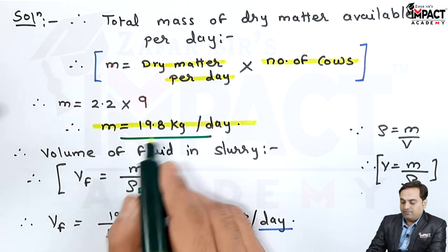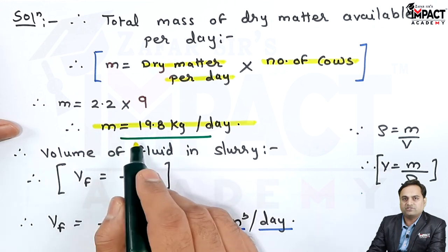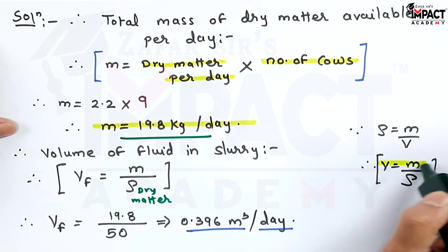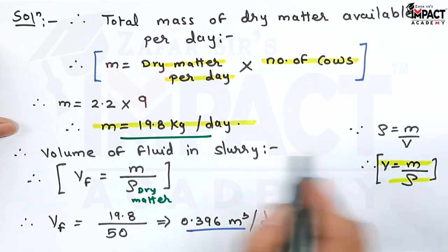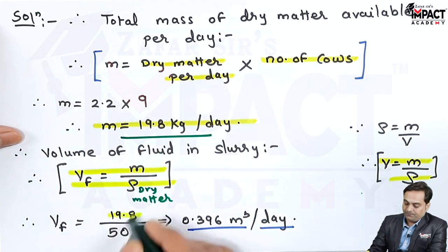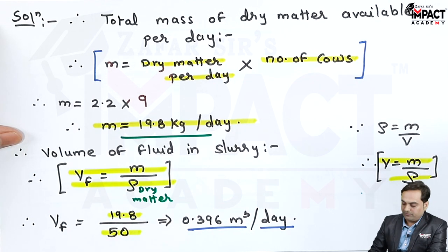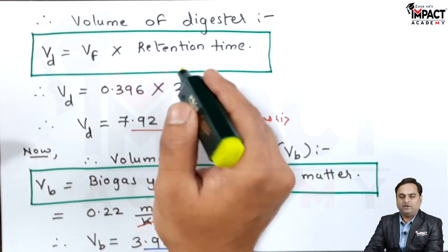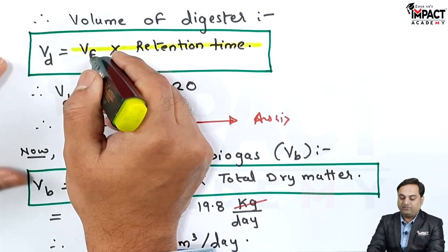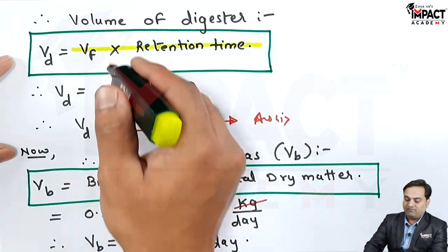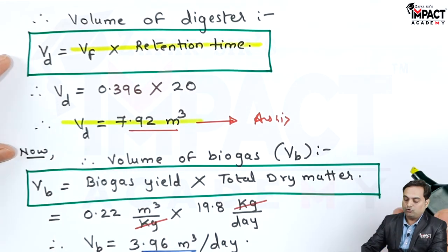After getting the mass, I will calculate the volume of this fluid because ultimately it will be mixed with water. Since density equals mass upon volume, volume becomes mass upon density. The volume of fluid in the slurry is mass upon density of dry matter: 19.8 divided by 50 kg per meter cube, giving a volume of 0.396 meter cube per day. Next, multiply Vf with the retention time — meter cube per day times days — the days cancel out and we get the volume of the digester in meter cube.